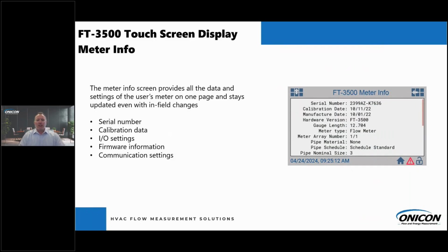The meter info, this is a great feature to have. We've seen it several times in the field: when you go up to the flow meter, the hanging display tags have been removed and you have no information outside of the serial number that you can provide to our tech support team. Now we have a meter info display available, so you're able to see the calibration information, the date, the serial number, and all that information is great to have. And when Mike was talking about the warranty we provide, you can still go in there and see if you're still under that 1-year warranty, or that 3-year manufacturer warranty, plus all the communication settings as well. Next.